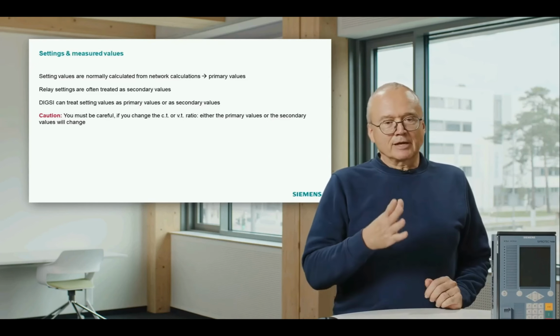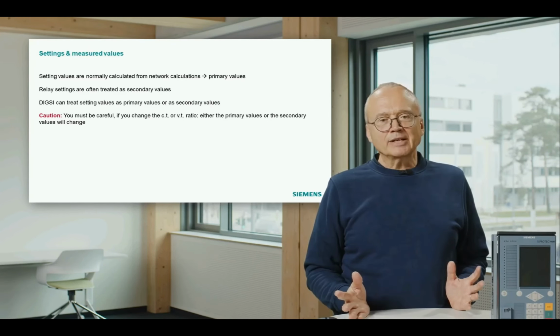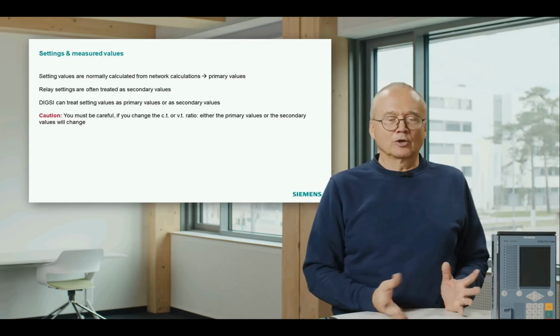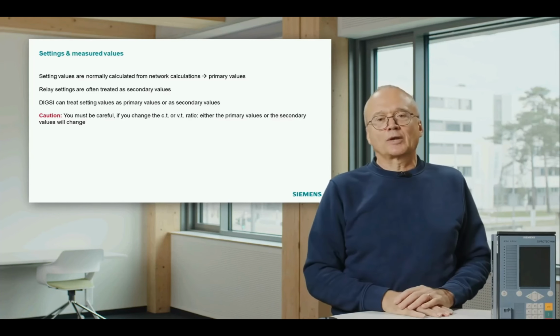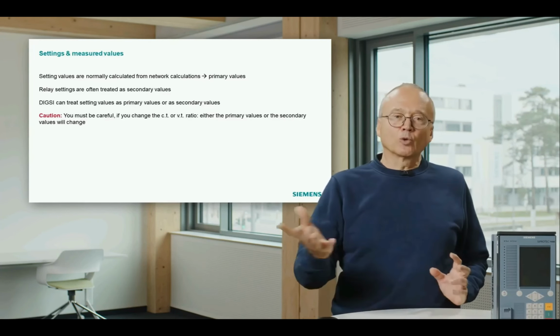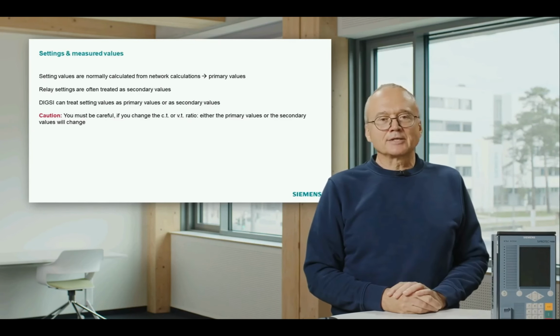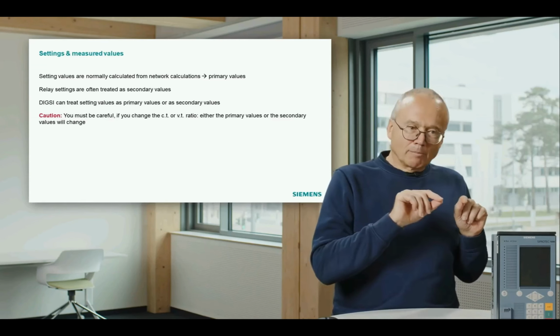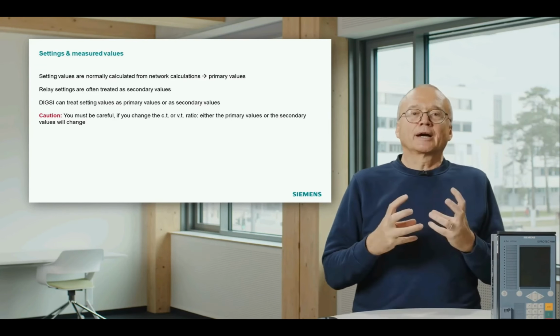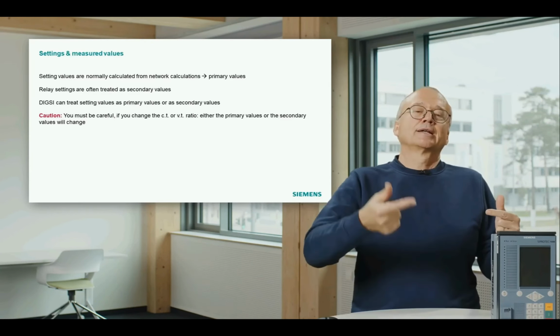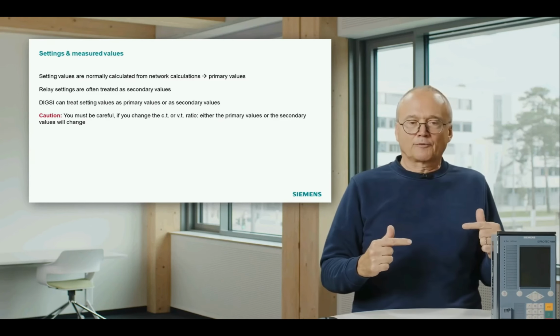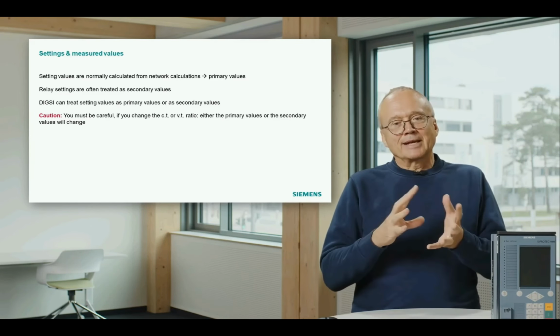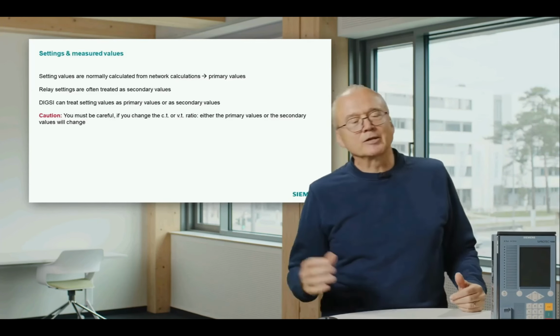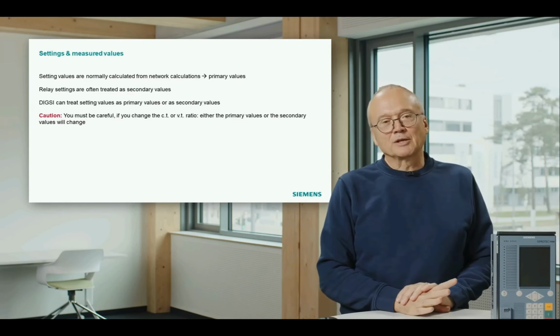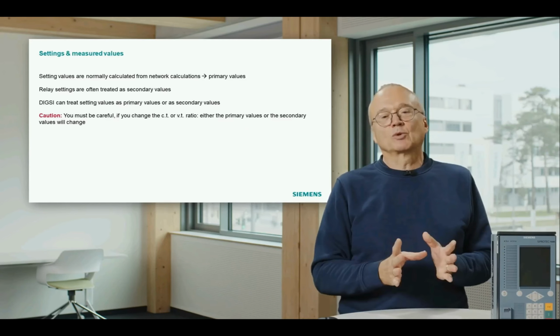One thing is, if you talk about a setting of an overcurrent relay, it's very easy to see, is it a primary value or a secondary setting value. If somebody tells you the setting is 1000 amp, you know, okay, 1000 amp looks like a primary value. If he says the setting is 1.5 amps, you know it's a secondary value. That's easy. But also in distance protection, where the setting values are impedances, you have to do the conversion, taking into account the ratio of the voltage transformer and of the current transformer. And then it's not visible if somebody says the setting value is 5 ohms. The 5 ohms can be a primary value or a secondary value. It must be clear what it is.